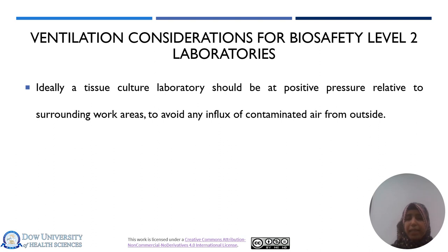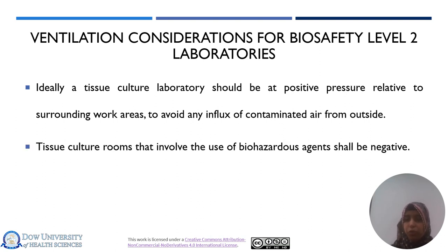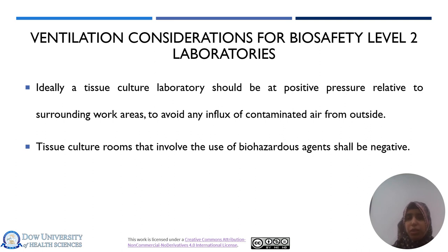Ideally, a tissue culture laboratory should be at positive pressure relative to the surrounding work area to avoid any influx of contaminated air from outside. Tissue culture rooms that specifically involve the use of biohazardous agents should be maintained at negative pressure. Following these rules when designing tissue culture laboratories will provide ideal conditions for working with different types of cultures.